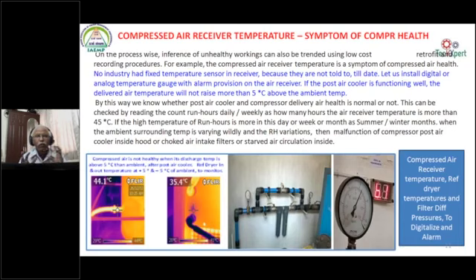The compressor is like a submersible pump working in air. It needs air to suck in, and it needs air to surround the compressor. Once the air is not surrounding the compressor, automatically the compressor will go to overload. So that is one aspect. For the refrigeration dryer, you can see the outlet temperature is ambient plus 5 degrees. Let us say ambient is 40, around 45 degrees is coming, whereas after the dryer it should be around 40 degrees, ambient minus 5 degrees. These are all the symptoms.